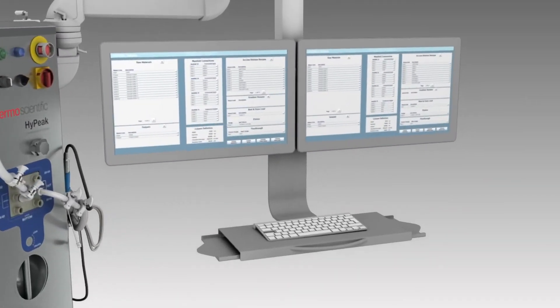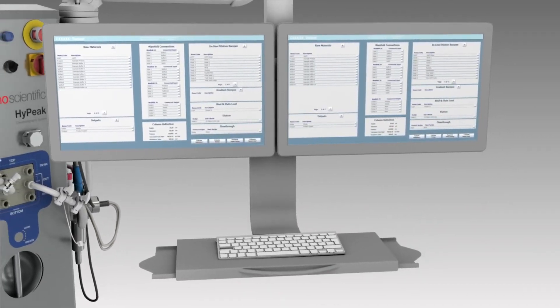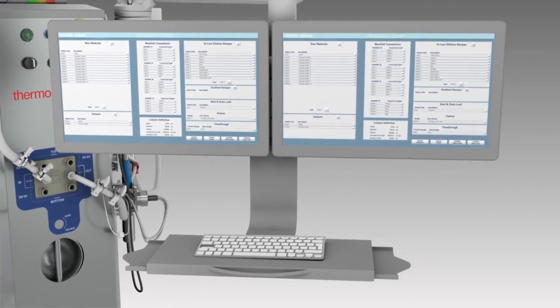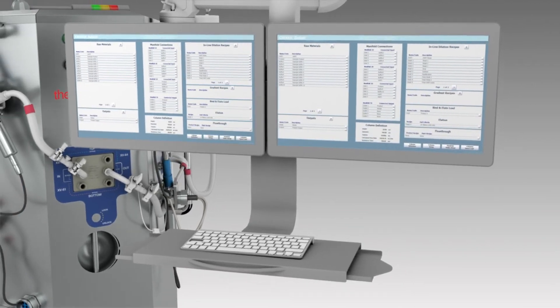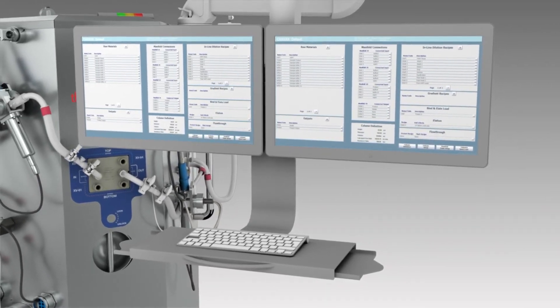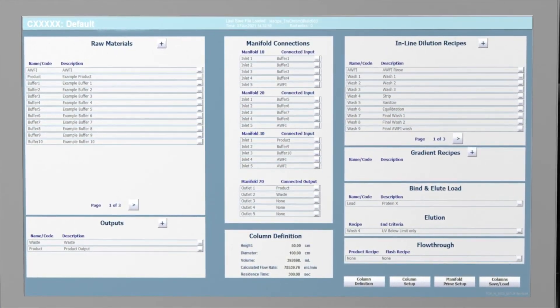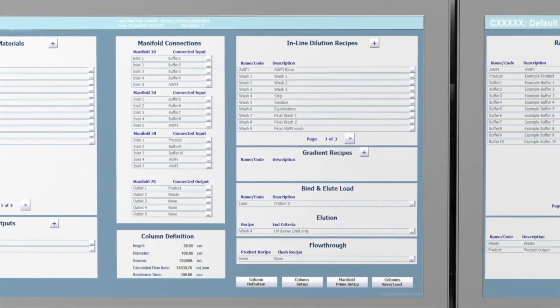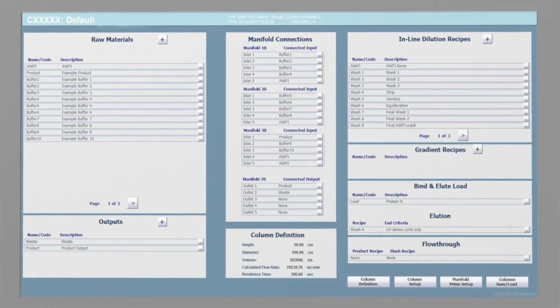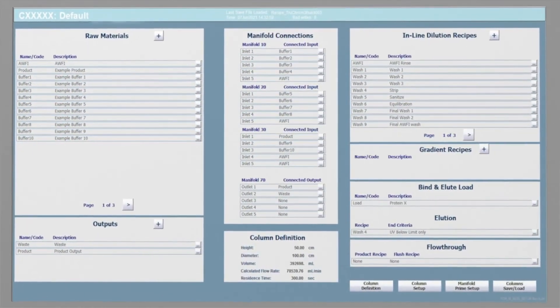The HyPeak Chromatography System provides the ability to leverage existing Delta V network infrastructure and allows ease of tech transfer, data integration and data storage. The simplified interface of TrueChrome software provides an enhanced user experience. Configurable user access, audit trail and batch reporting are available as standard features.